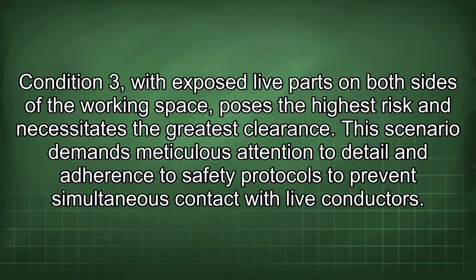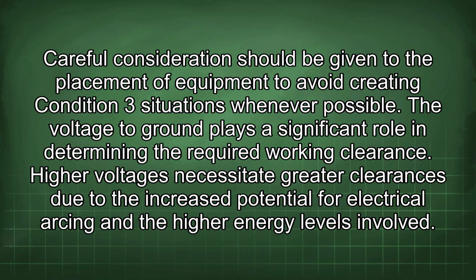greatest clearance. This scenario demands meticulous attention to detail and adherence to safety protocols to prevent simultaneous contact with live conductors. Careful consideration should be given to the placement of equipment to avoid creating Condition 3 situations whenever possible. The voltage to ground plays a significant role in determining the required working clearance. Higher voltages necessitate greater clearances due to the increased potential for electrical arcing and the higher energy levels involved.